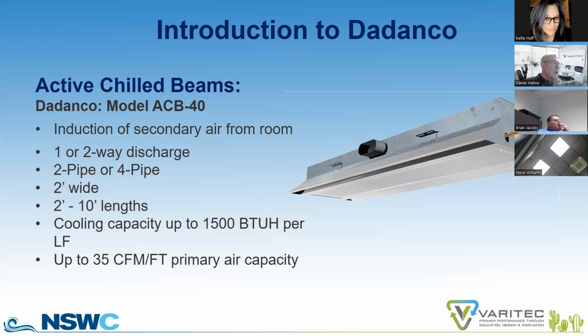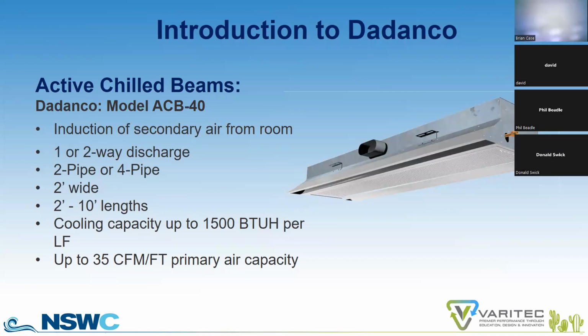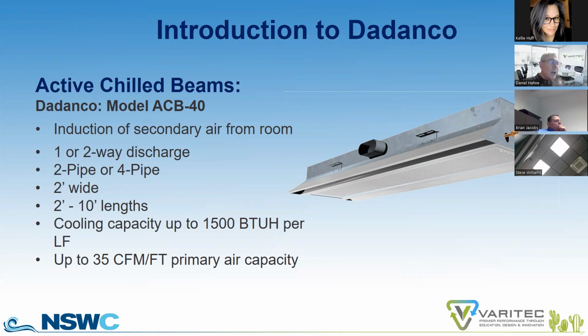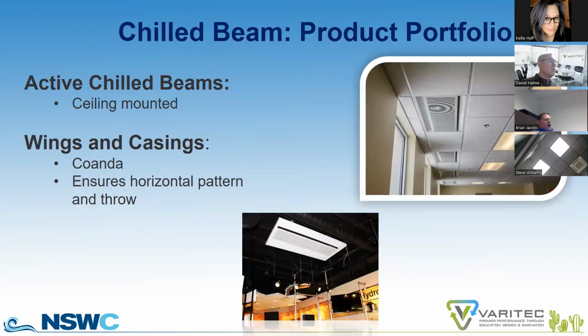out of these beams. And in a conference room where you see wide load swings, you may want to bump the airside component to more than 5 to 10 CFM per lineal foot, maybe 15, 20, up to maybe even 35, depending on the application. But when you do that, you reduce the beam efficiency. But it is an excellent solution, providing you have a manufacturer that builds beams that are low sound at high flow rates. Then it is certainly an option for strategic zones that see occupancy density swings. Certainly is a possible solution.